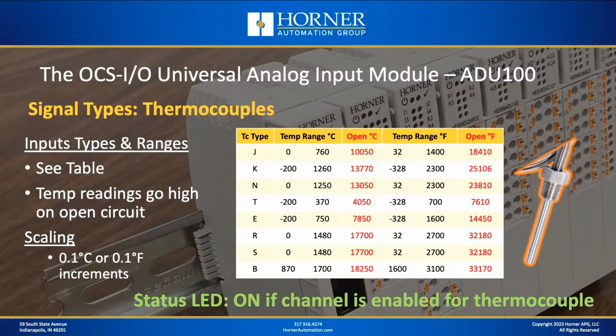And generally, well, always, those values that are reported are larger than the highest range value that could be reported for that thermocouple type. Now, the values are, just like RTDs, already scaled for temperature in degrees Celsius or degrees Fahrenheit increments. From a status LED standpoint, the thermocouple module only turns on the LED if that channel is enabled for thermocouple. So you can't really use that LED for detecting an open circuit or anything. That's going to be based on the readings coming back that you're going to detect an open circuit.